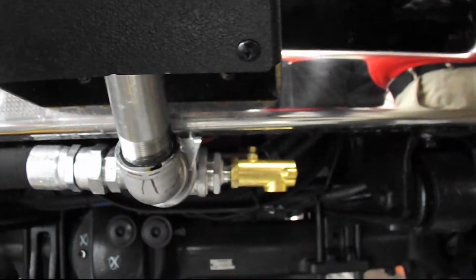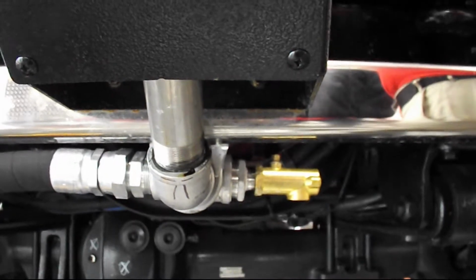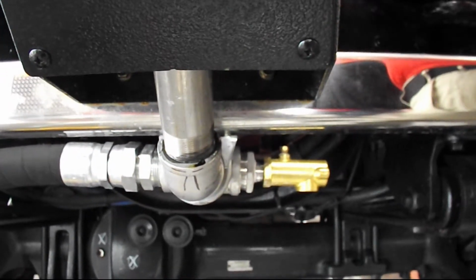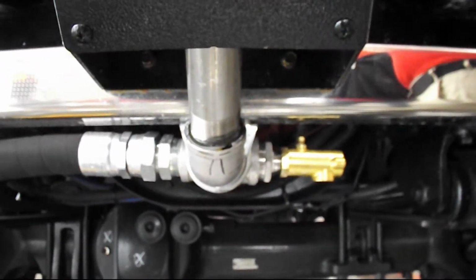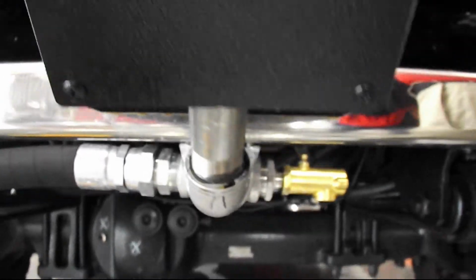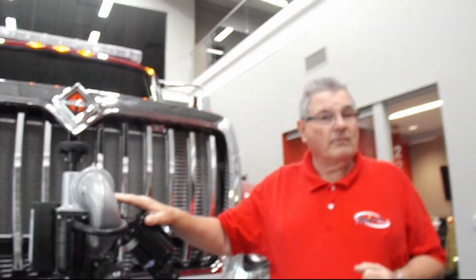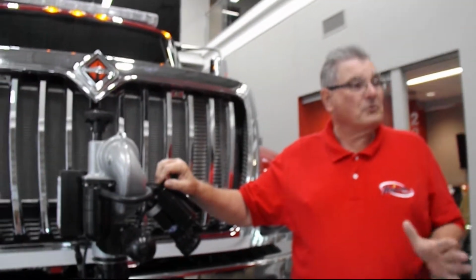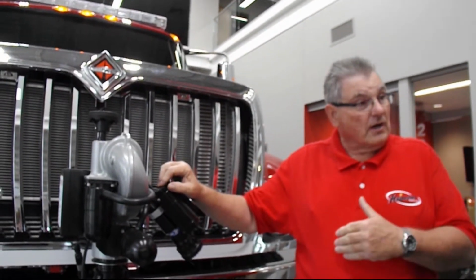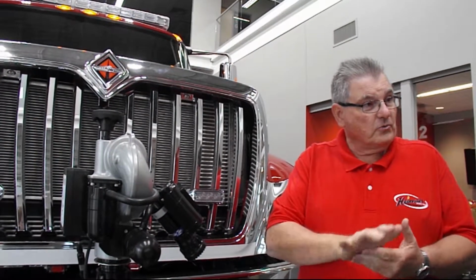So that valve is always open until you put pressure to it, but then it closes. At about 5 pounds, she closes. There's just a little spring diaphragm in it. So if it ever keeps running, sometimes there's a piece of crap in there. So what guys will say when you shut this off is, 'hey, there's water running out the bottom of the truck.' Well, there should be, and that's how it stays dry, because it only closes when there's pressure.